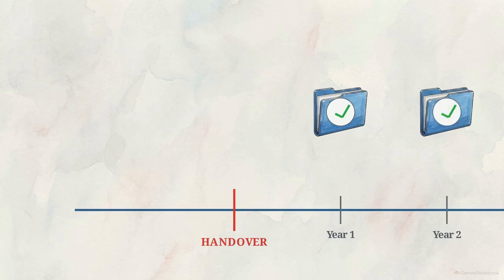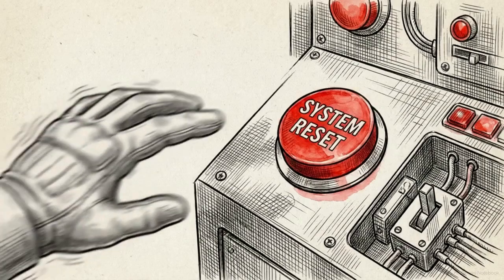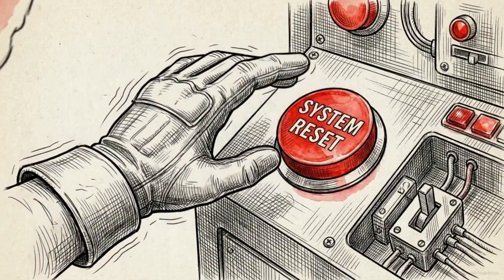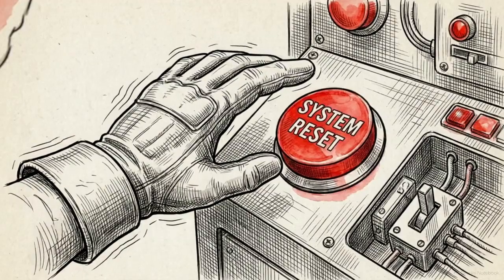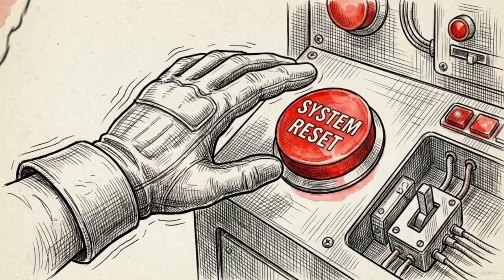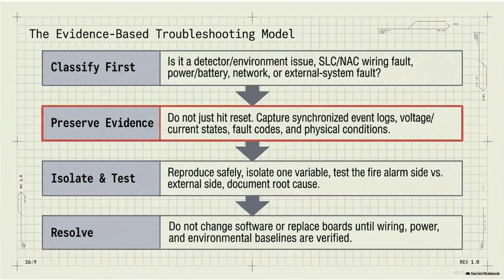Human failure remains a significant threat. When a nuisance alarm sounds, the immediate instinct is often to blindly hit reset to clear the board. This troubleshooting model replaces panic with process. Operators must capture synchronized event logs and voltage states before resetting. Software settings should never be altered to fix a physical wiring or environmental fault.